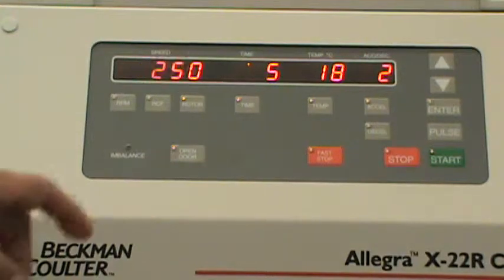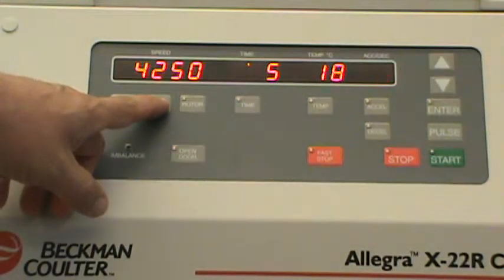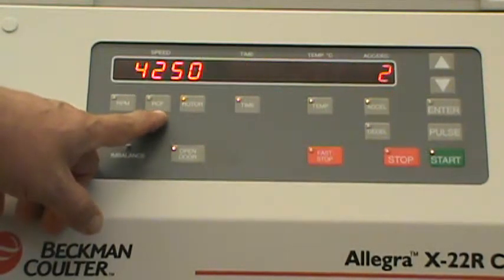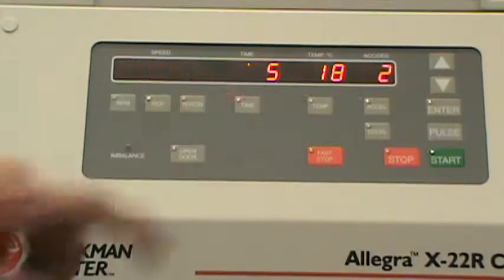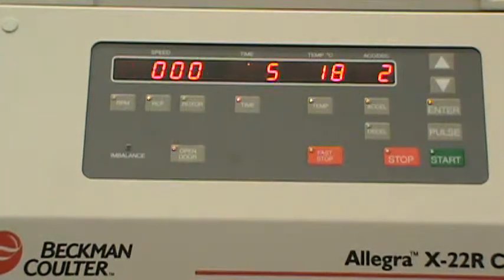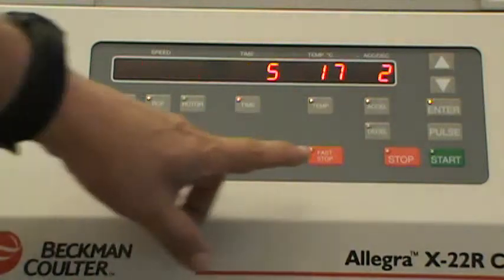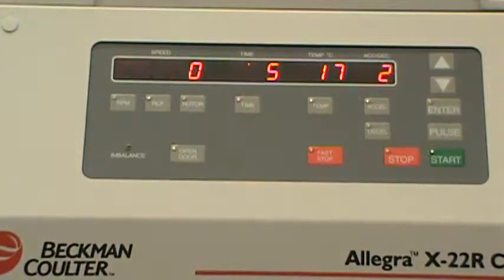We can adjust how fast we want things to spin in this centrifuge. This dial right here is the RCF, or relative centrifugal force dial. It will spin the material in the centrifuge at that many times the gravitational force of the Earth. So if we're spinning it with the RCF set at 2,000, that means we'll be spinning the material at 2,000 times the force of gravity. Again, when you select that button, you have to press enter.